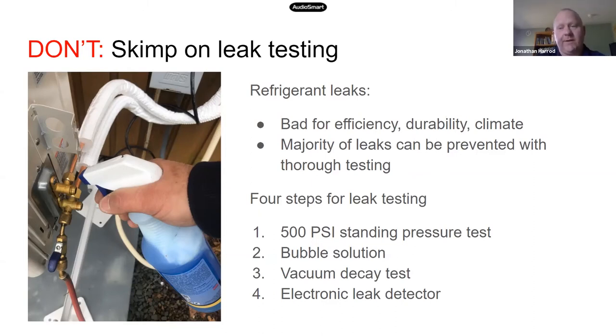Then we have to evacuate the system to get the air, the nitrogen, and any residual moisture out of the system. That's an important step in startup, but it also gives you one more chance to check the tightness of the system. You evacuate the system down to a really deep vacuum, almost as deep as outer space, and then you make sure that it's able to hold that vacuum for a certain amount of time.